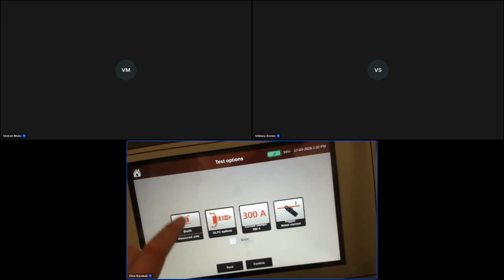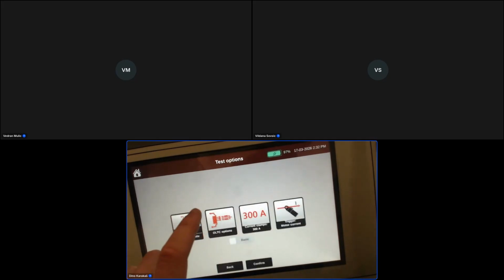We can go basic and advanced. You can see here we can perform measurement on both sides, high voltage side or low voltage side. For this opportunity, we will do both sides. The operating direction can be changed here. It can be same or reversed. You see the change of the direction of these arrows.